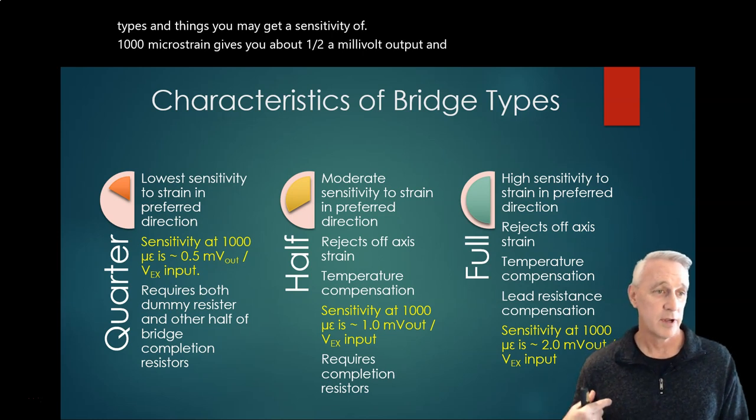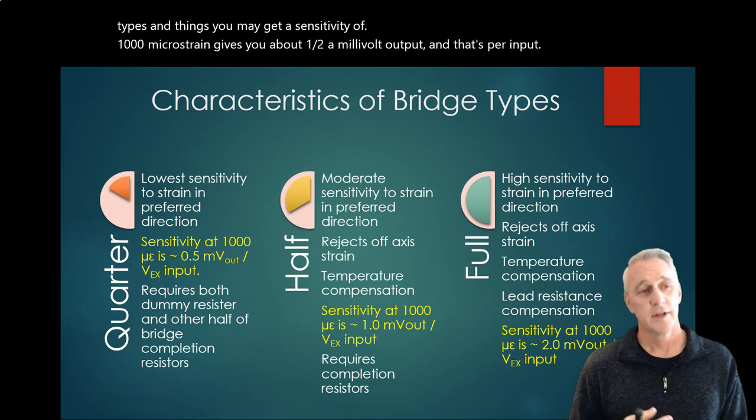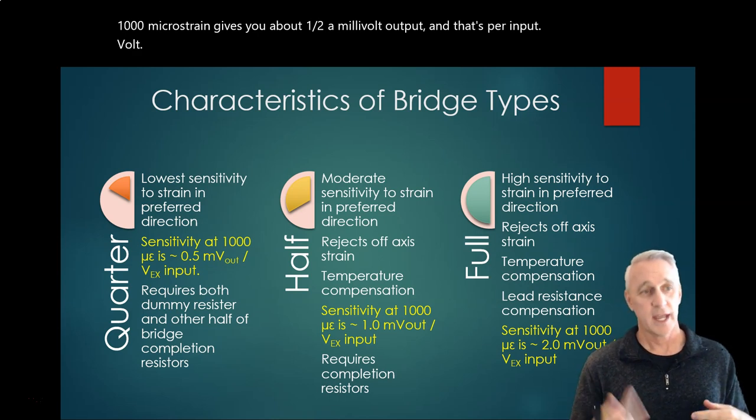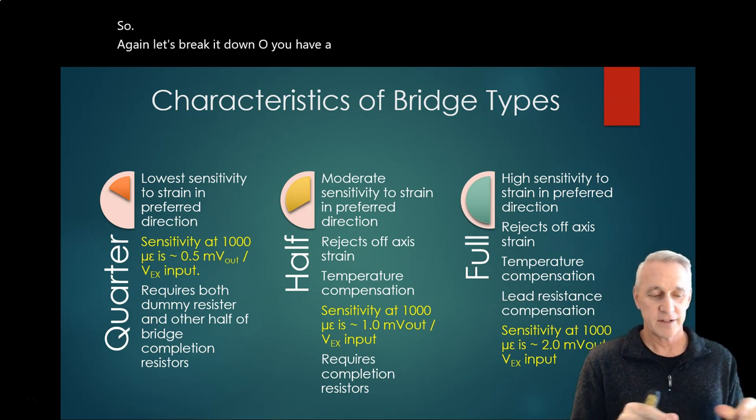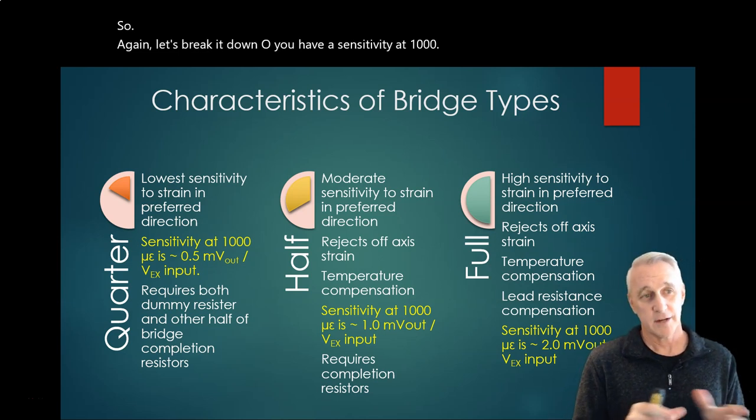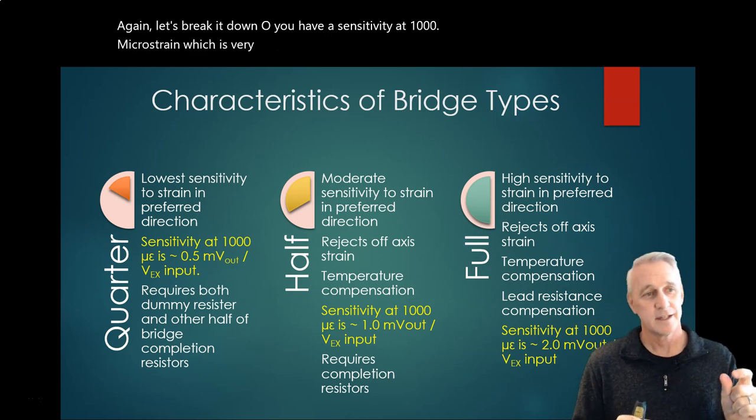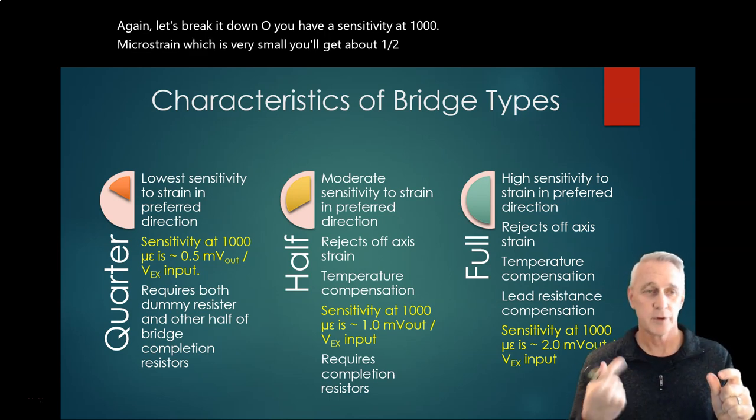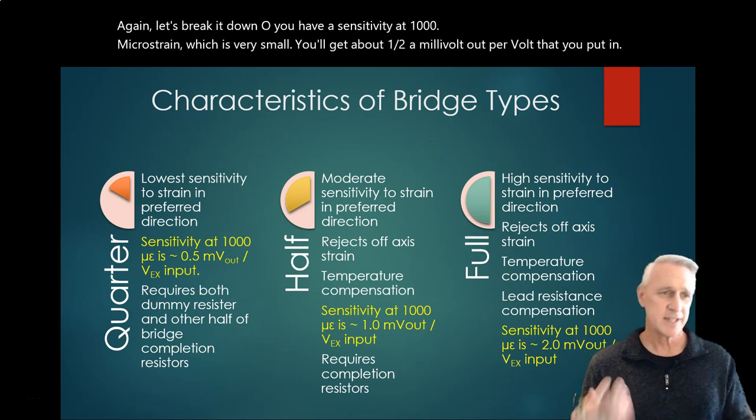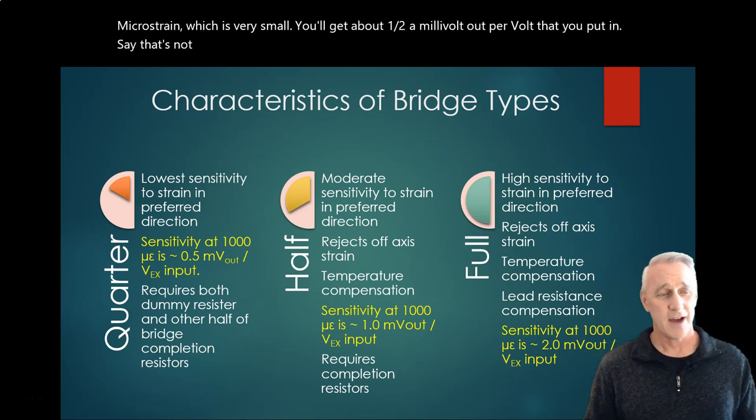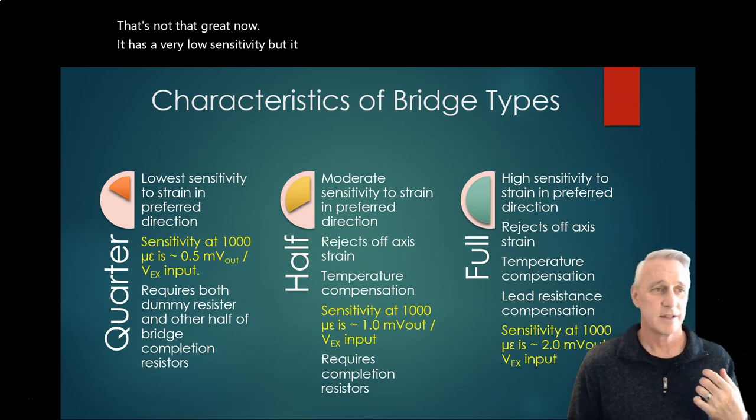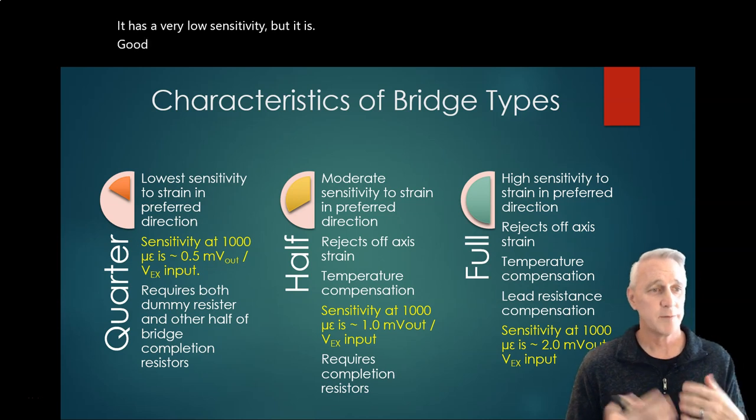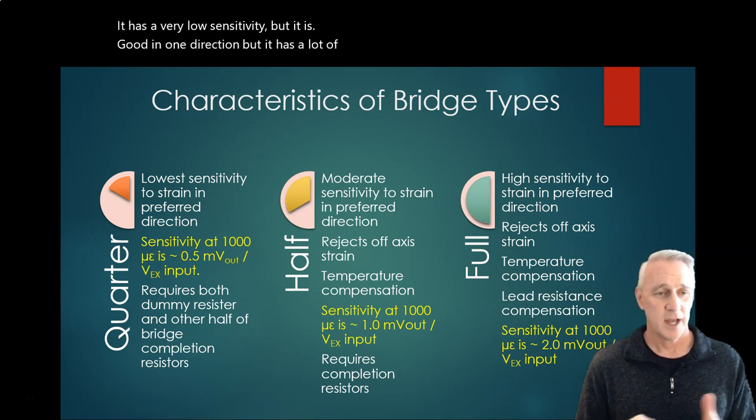So again, let's break it down. So you have a sensitivity at 1000 microstrain, which is very small, you'll get about a half a millivolt out per volt that you put in. That's not that great. Now, it has a very low sensitivity, but it is good in one direction. But it has a lot of other issues with dealing with noise and other things because it doesn't compensate for temperature changes. It doesn't reject off-axis issues. So it also is subject to all those things changing as well.